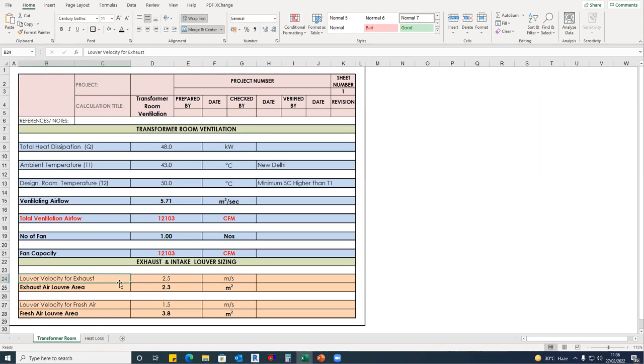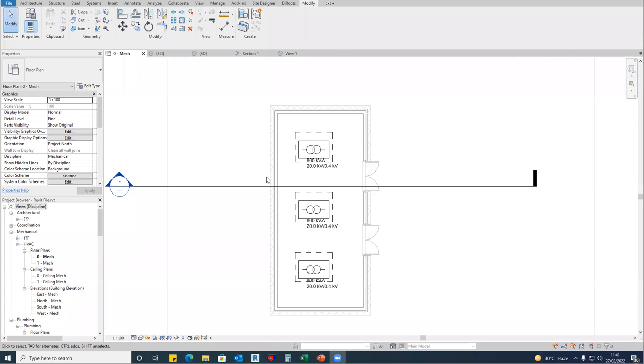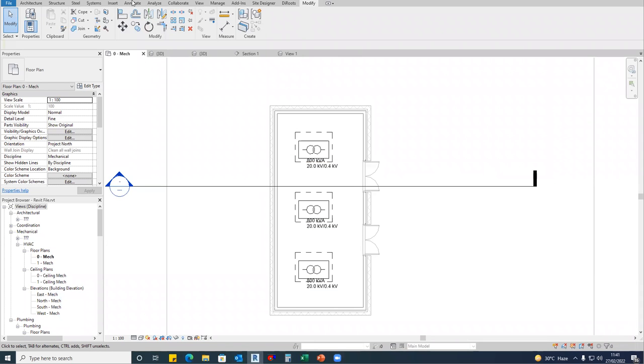Now for the louver, I'll design on 2.5 for exhaust and 1.5 for fresh air. Okay, it should not be more than 2.5. And once you divide the flow rate by the velocity, you'll get the area. Okay, and similarly for fresh air also, Q by V, you'll get the area. Now let's model this system. Okay, so our flow rate is how much? 12,103. Okay.